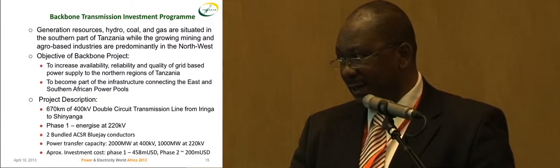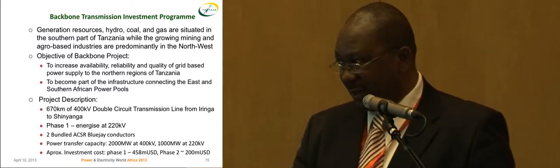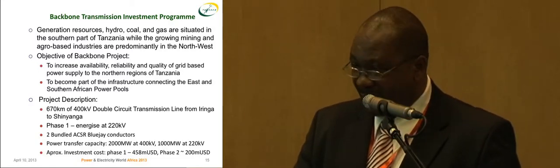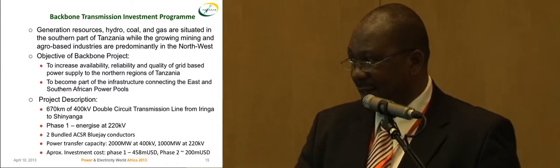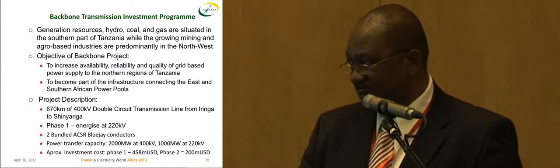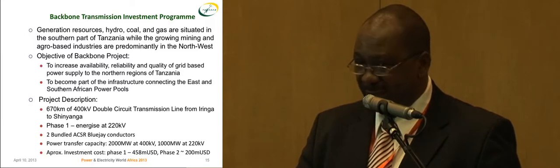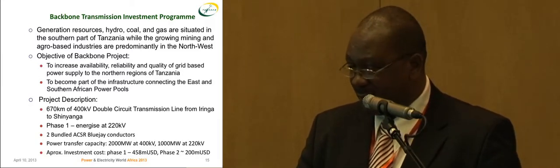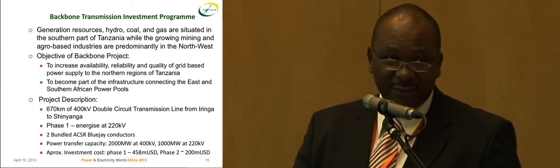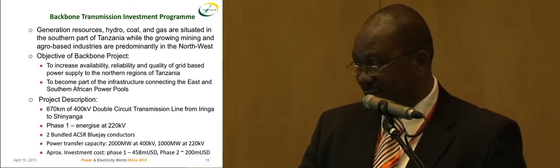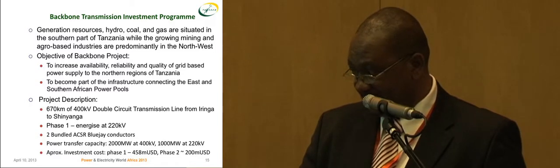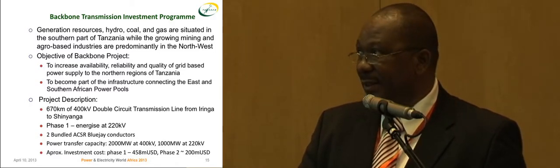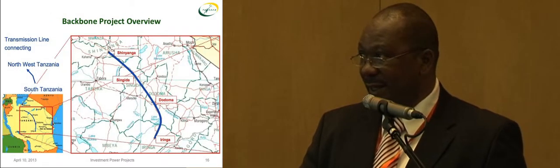But currently we do not need all that much power, so phase one will energize the line at 220 kV with a capacity of about 1,000 megawatts. Later on, in phase two, we will upgrade the substation transformation to bring up the voltage level to 400 kV. Maybe this is my last slide.